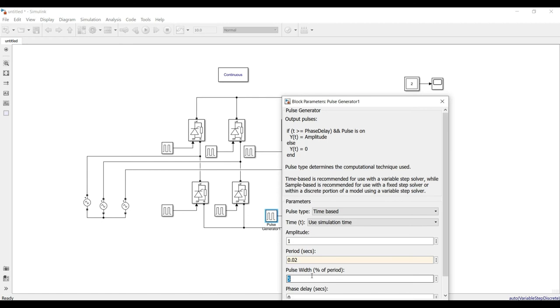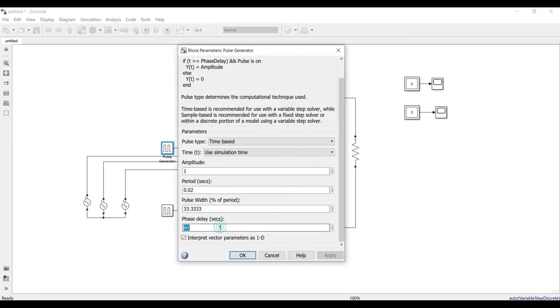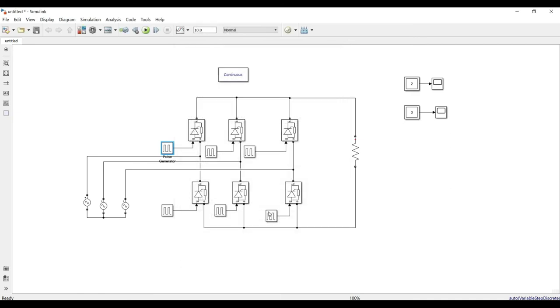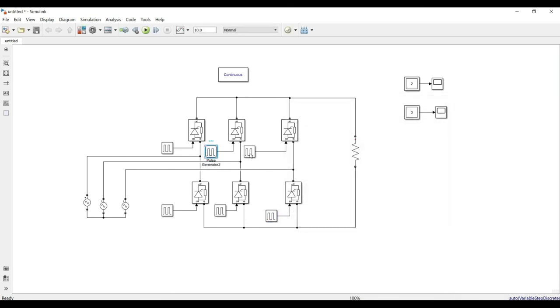The phase delay must be entered in seconds, not degrees. The conversion is: delay_in_seconds = (0.02 / 360) × angle_in_degrees. I copy this formula and paste it for each thyristor's phase delay, then adjust the angle value for each one.